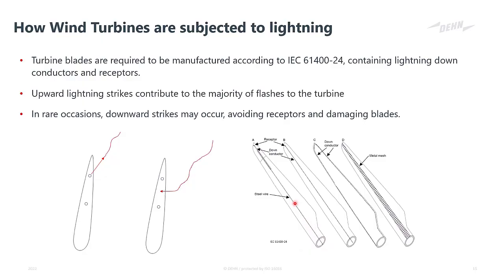Now, along this down conductor, there are connections to the outside of the blade with what is known as lightning receptors. These lightning receptors look like coins. They're small metallic parts that look exactly like coins along the blade itself, connected to this down conductor. Now, knowing that we have upward strikes on tall structures, and so on wind turbines as well, the charge content will accumulate at the base of the tower, and the current will move up the tower through the reinforced system up to the nacelle. The current will then move through this conductor in the blade and then exit the blade, as you can see here, through one of the lightning receptors, and it strikes to cloud. So all the lightning current is focused on that single receptor, and that receptor will have its limitations.